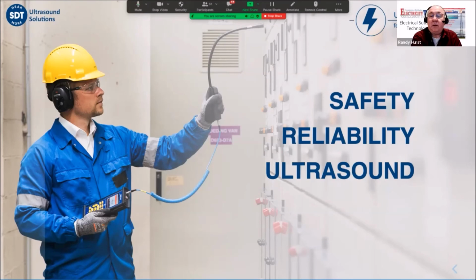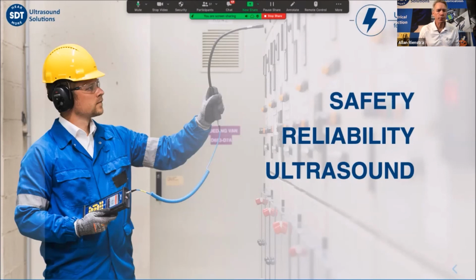Here's another one: what is the voltage threshold above which ultrasound becomes useful? I can detect arcing in a 110 volt light switch. But corona, in terms of partial discharge, is a broad term that encompasses arcing, tracking, and all of these problems. Arcing can occur at very low voltages. Corona only occurs, I believe, around 2000 volts, and I'm sure someone here is smarter than me and will correct me. But there is a threshold for corona where above a certain voltage you can hear it, and below it, it just doesn't exist ultrasonically.